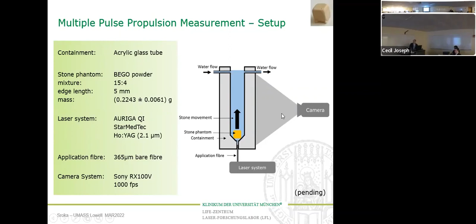What we did is we put our phantom stones within this kind of cylinder. The laser system and the fiber come from the bottom, and we push the stone upwards from the bottom due to this pressure wave. And that we recorded with a fast camera, and then we track the stone. We can see clearly how it is moving, and we can clearly identify the up and down movements of the stone.